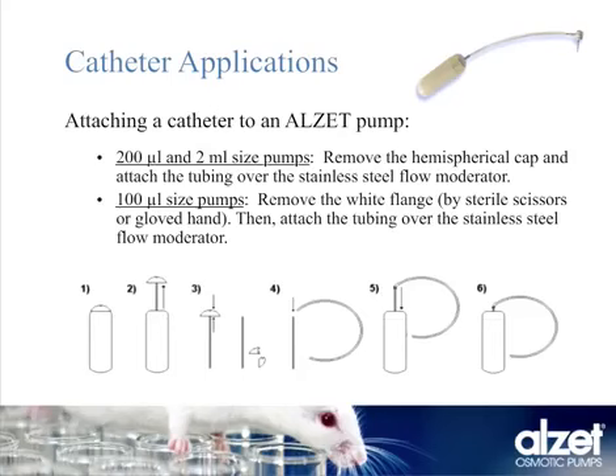Now it's a little different with the smaller 100 microliter size pumps. This pump is so small that we couldn't fit a cap at the end of the flow moderator. What you'll have to do is remove the entire white piece at the tip of the flow moderator, and this is what we call the flange. You can either find some sterile pliers to break the flange off, and that's what you see in step 3. Or you can carefully slide the flange down the flow moderator and remove it from the opposite end. When removing the flange correctly, you'll be left with a clean stainless steel tube, and you can see that in image 4. And from there, you can attach your catheter at either end.